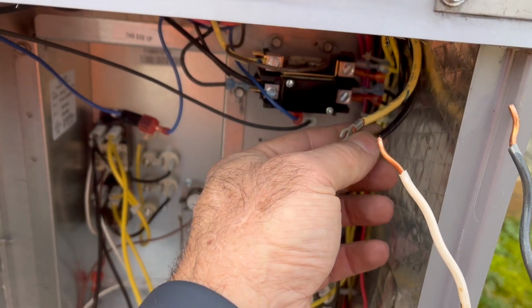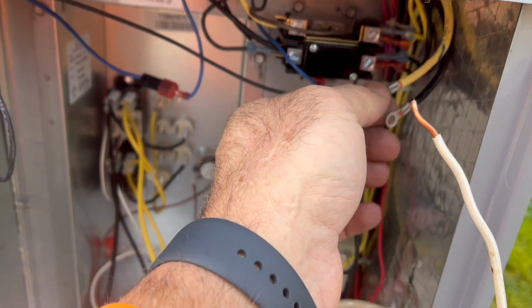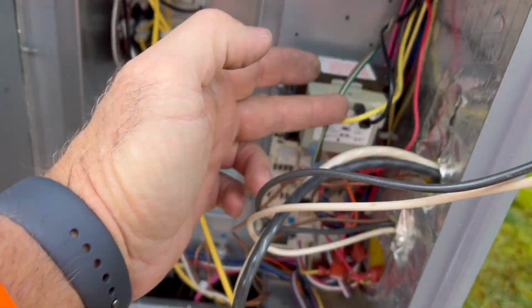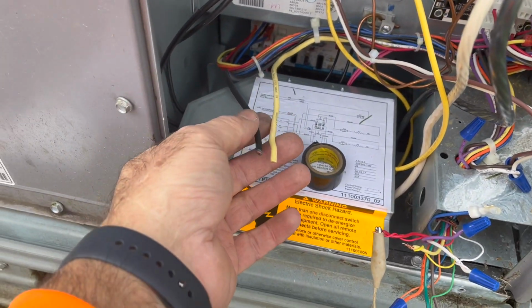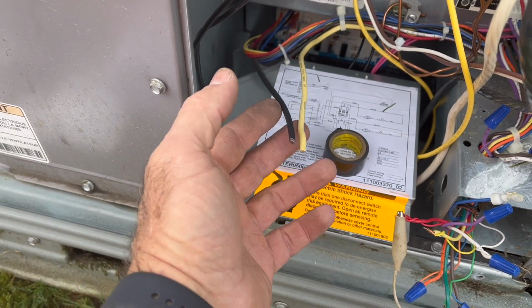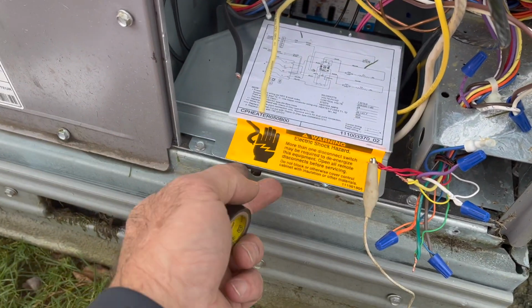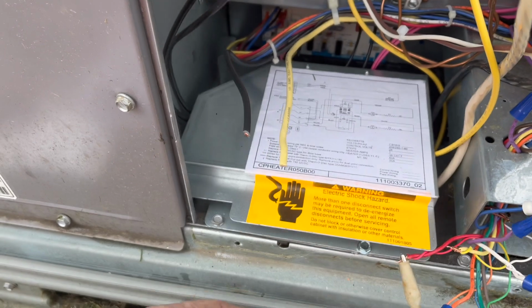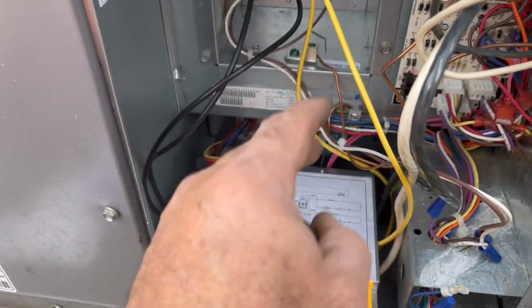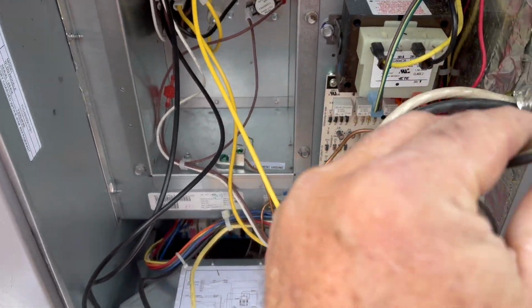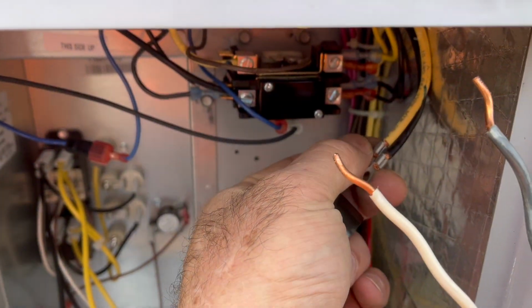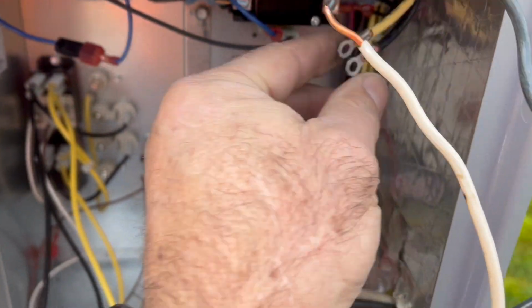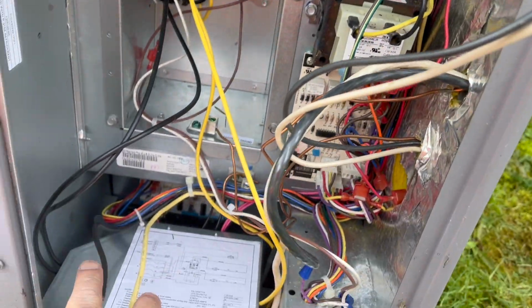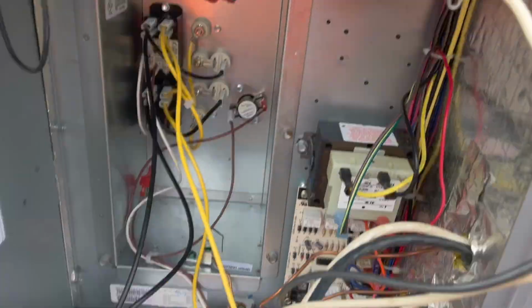Rather than the way Carrier does this, with these on the contactor going down through this bundled harness to the bottom, presumably where the single point power supply would be for the heat kit, I'm just gonna make one connection instead of two, and tape these ends up so they don't get into anything. Taking out one wire nut might prevent a problem later on. So that's what we're going to do.